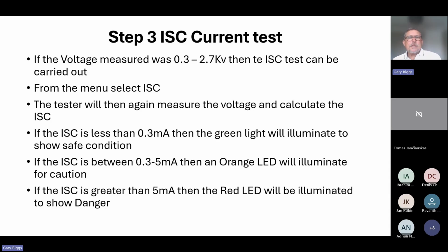Now, if the ISC is less than 0.3 milliamps, then a green light will illuminate, and it shows that the system is not a hot system. No 11 kV system is considered safe as such, but it's safe for the guys to continue. If the ISC is between 0.3 and 5 milliamps, then an orange warning LED will illuminate, telling them that potentially the cross member has a voltage with potential current, and the pole itself will have voltage on it with potential current.